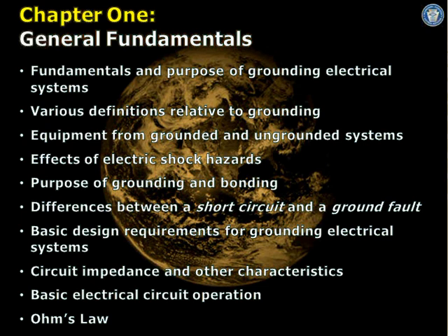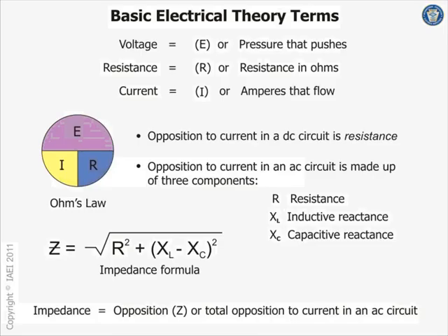Grounding and bonding is safety. Well, proper operation of the system is the most important thing, because if the system doesn't work, it's unsafe. So it has to work properly. So that's why you bond the neutral and so forth. And then it has to work safely. So we'll talk about the difference between the short circuit and the ground fault, design requirements for a grounded electrical system, circuit impedance, and basic electrical operation. So let's go ahead and do a few of these.